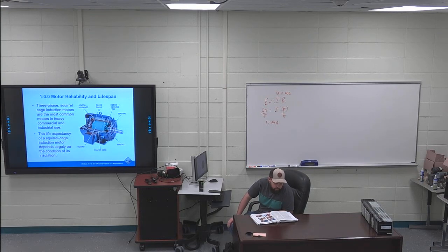Moving on to page 2, I've got the overloading section highlighted. Overloading a motor can cause overheating and eventual bearing failure or premature insulation failure of the windings. Overloading usually occurs because the driven load has been changed to accommodate a higher capacity, heavier capacity, or increased duty cycle. When the driven loads are altered for these reasons, existing motors must be evaluated to be certain they can withstand the new load.